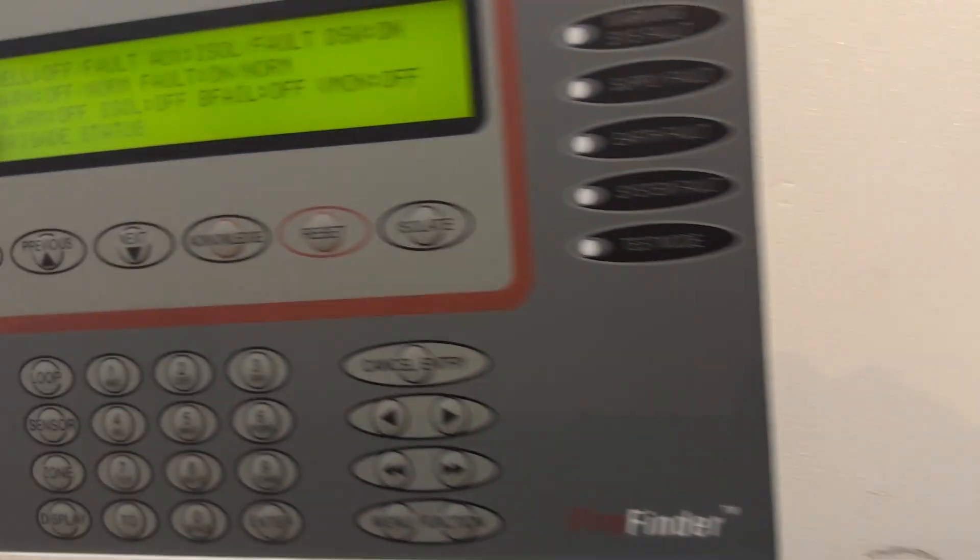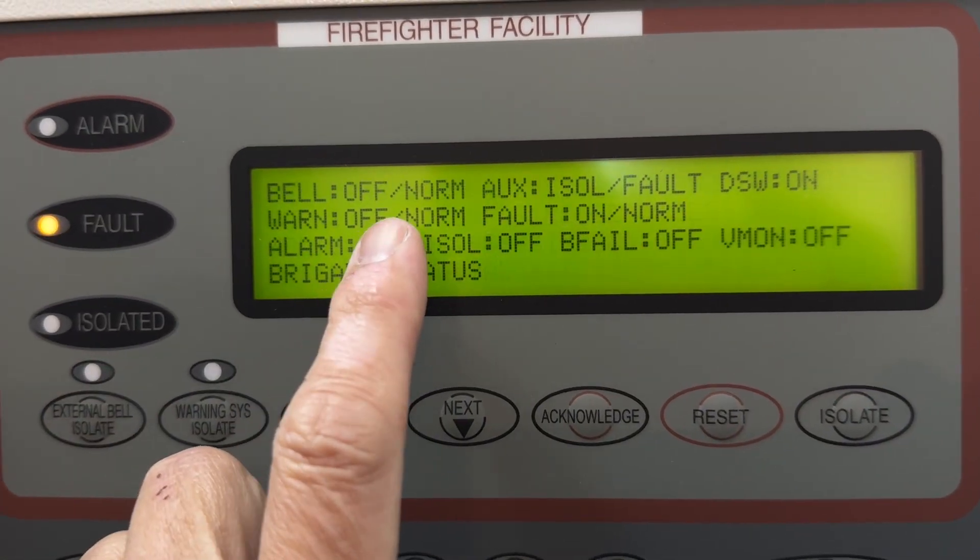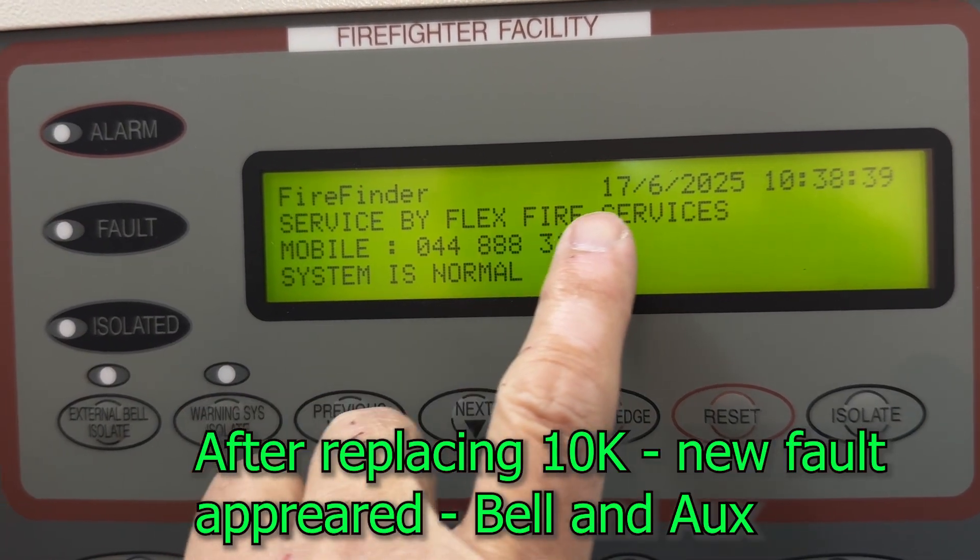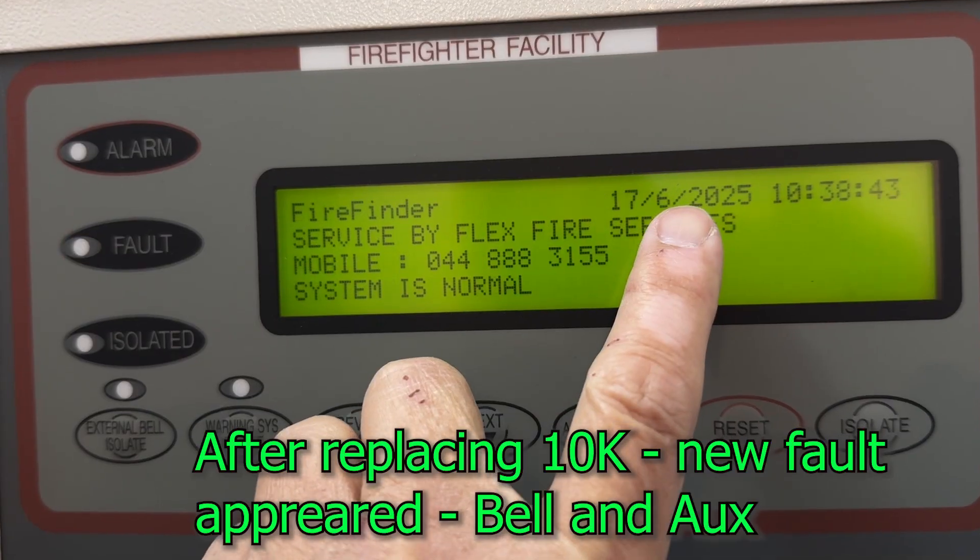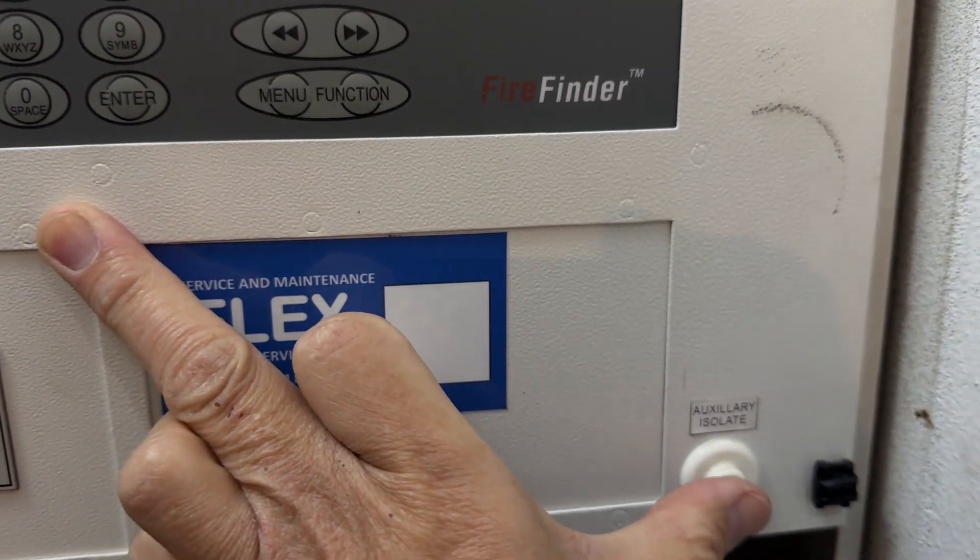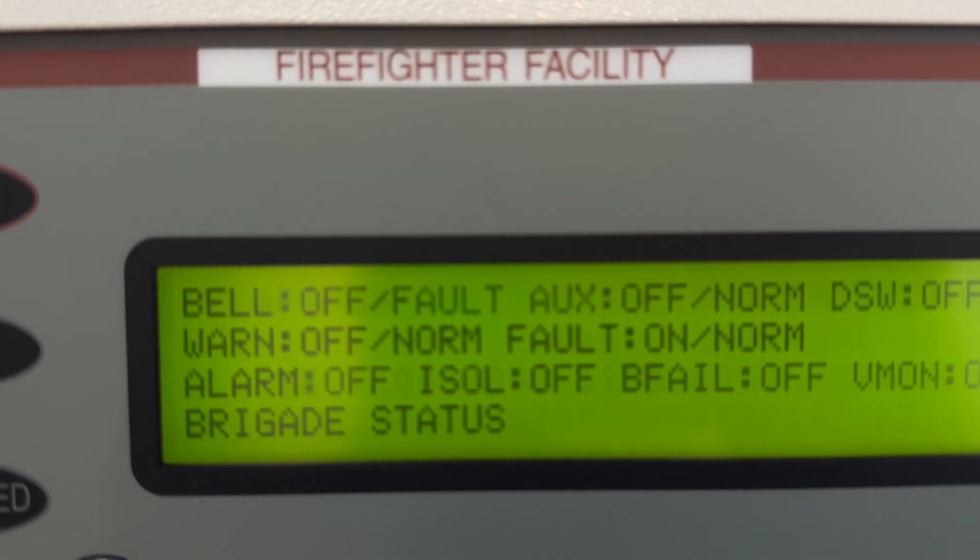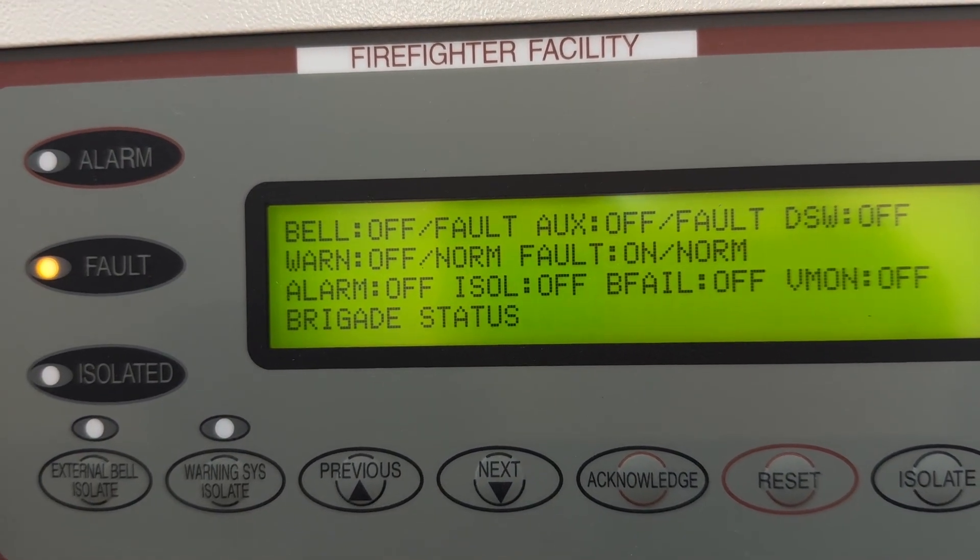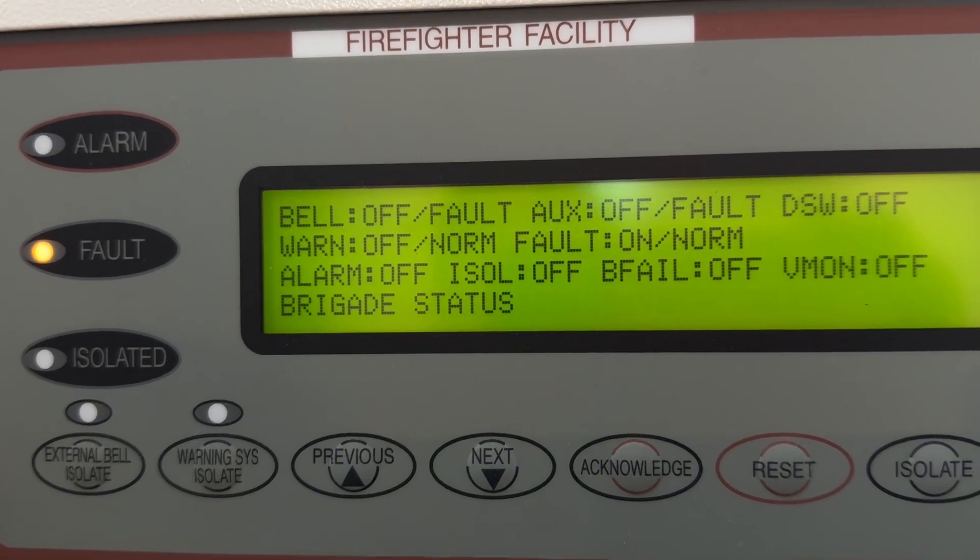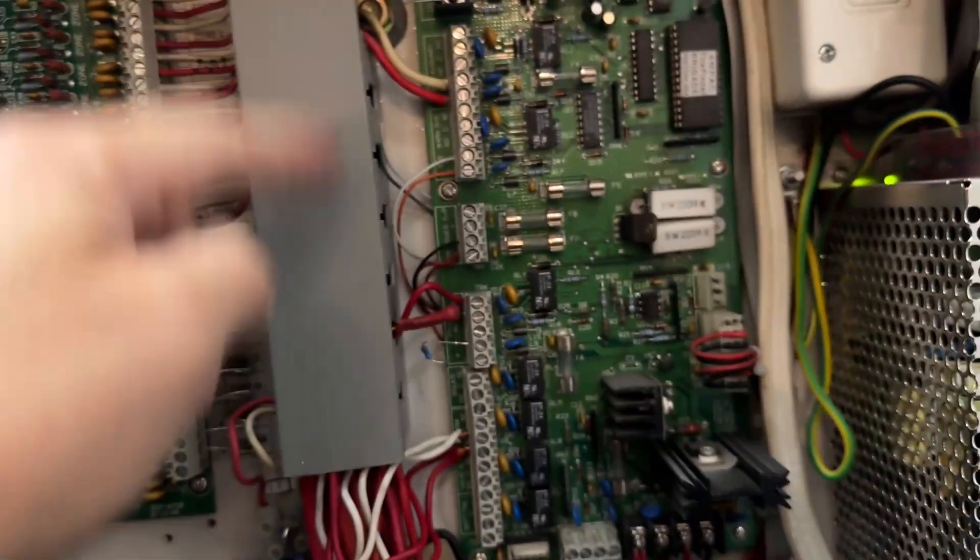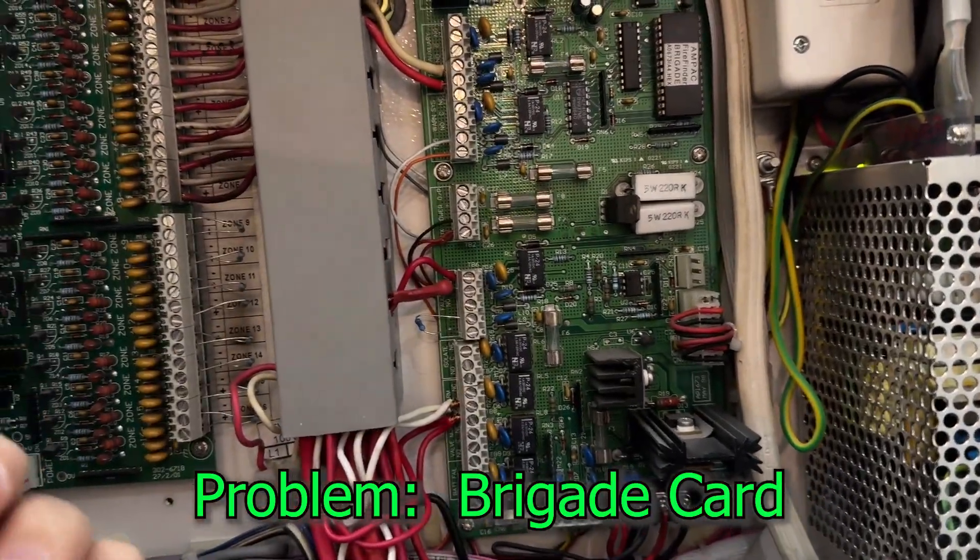Now let's look at here. If you will see, I have a bell off fault, and then I have an auxiliary isolated fault. It's isolated because it's isolated right now there because of this button. All right, if I press that button, that's the isolate. And you will see that I still have a problem with my auxiliary and my bell, which are both off. Right, so what's the problem here? Definitely it's not coming from that relay card. It's coming from the entire brigade card. We're going to replace the brigade card and let's see what will happen.